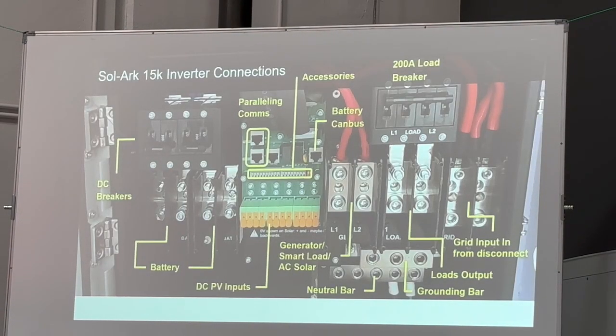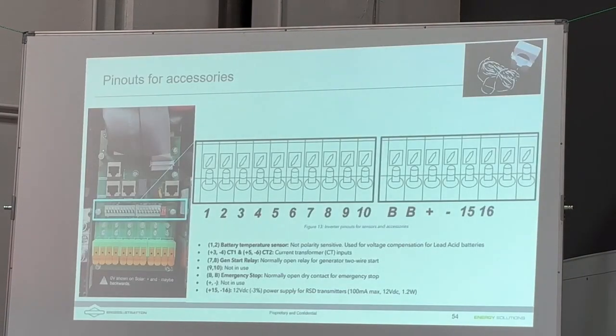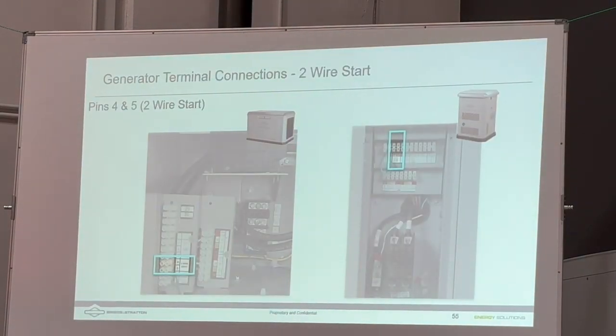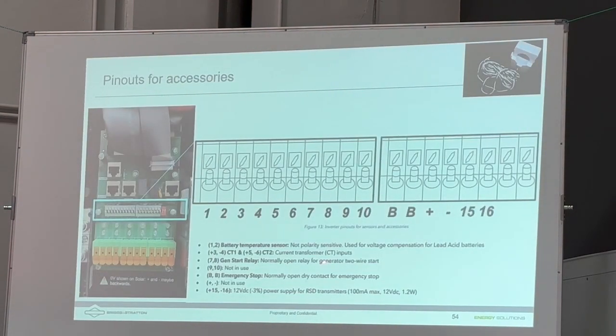Okay, so one more time, integrating a generator, we can come through the gen port or we can come through a transfer switch and come into the grid port. Got both. That's the pin out again. So let me just show you, if you are doing the 2-wire start, so remember 2-wire start here is pins 7 and 8. These pins are normally open. It's a dry contactor, meaning you just basically have the pins and they're not touching each other. And when the inverter wants to start up the generator, it connects those two pins inside. It's just a little switch inside that does that.